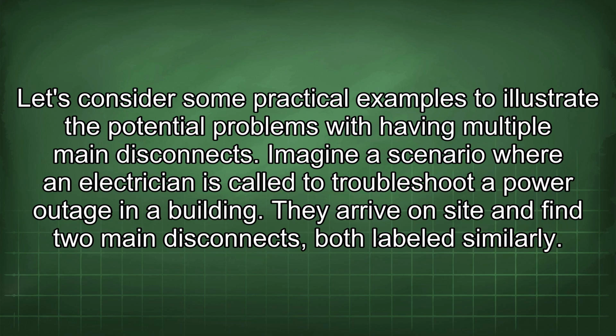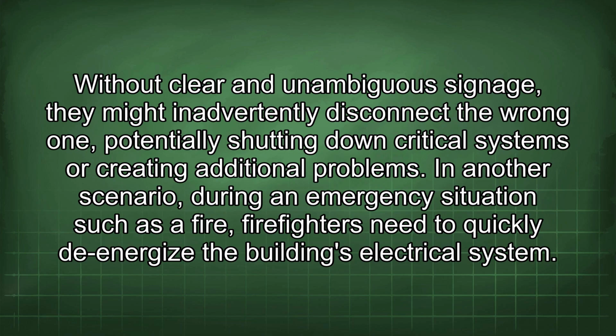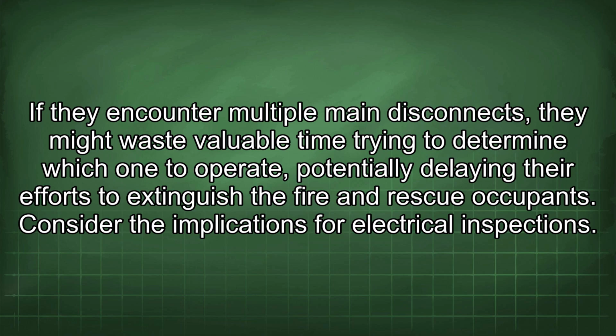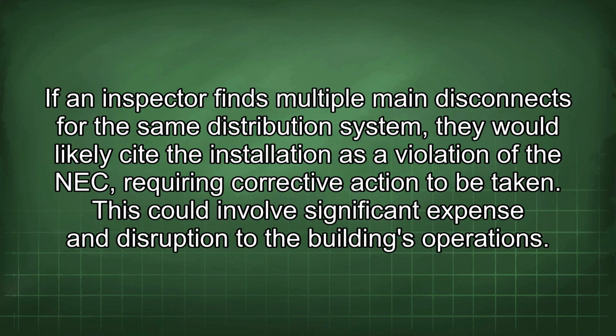Let's consider some practical examples to illustrate the potential problems with having multiple main disconnects. Imagine a scenario where an electrician is called to troubleshoot a power outage in a building. They arrive on site and find two main disconnects, both labeled similarly. Without clear and unambiguous signage, they might inadvertently disconnect the wrong one, potentially shutting down critical systems or creating additional problems. In another scenario, during an emergency situation such as a fire, firefighters need to quickly de-energize the building's electrical system. If they encounter multiple main disconnects, they might waste valuable time trying to determine which one to operate, potentially delaying their efforts to extinguish the fire and rescue occupants. Consider the implications for electrical inspections. If an inspector finds multiple main disconnects for the same distribution system, they would likely cite the installation as a violation of the NEC, requiring corrective action to be taken.